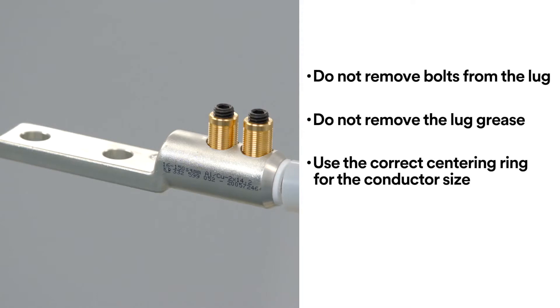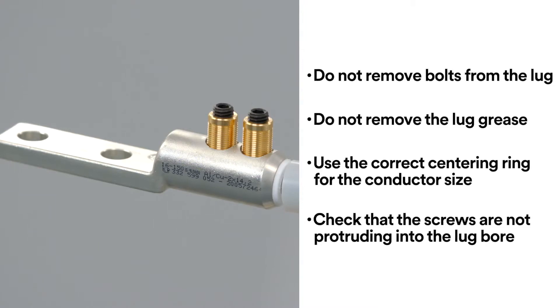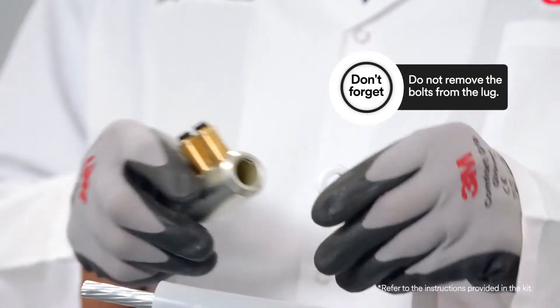Make sure that you use the correct centering ring for the conductor size. You also need to check that the screws are not protruding into the lug bore. Once you've done these checks, it's time to install the lug.